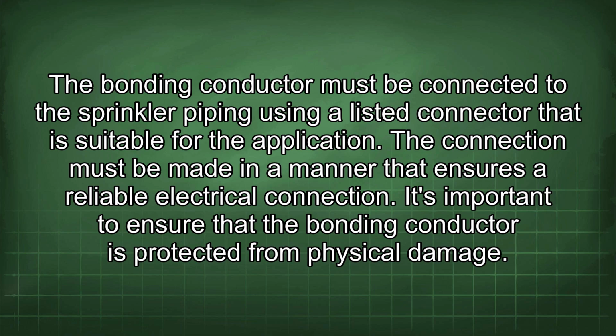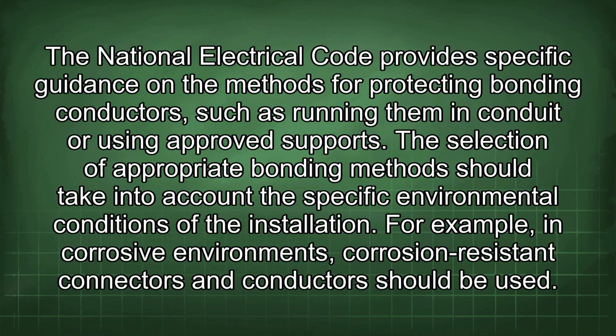The bonding conductor must be connected to the sprinkler piping using a listed connector that is suitable for the application. The connection must be made in a manner that ensures a reliable electrical connection. It's important to ensure that the bonding conductor is protected from physical damage. The National Electrical Code provides specific guidance on the methods for protecting bonding conductors, such as running them in conduit or using approved supports. The selection of appropriate bonding methods should take into account the specific environmental conditions of the installation. For example, in corrosive environments, corrosion-resistant connectors and conductors should be used.